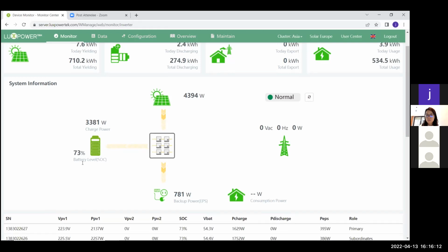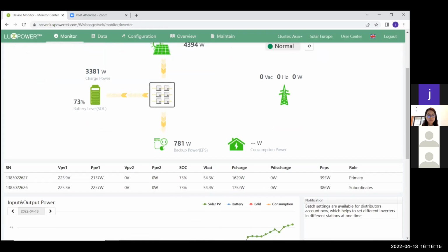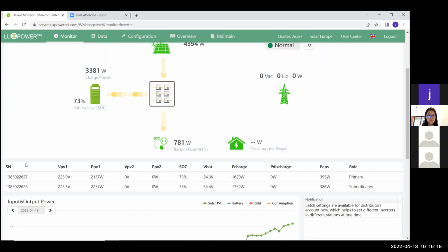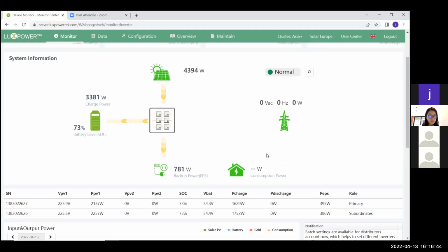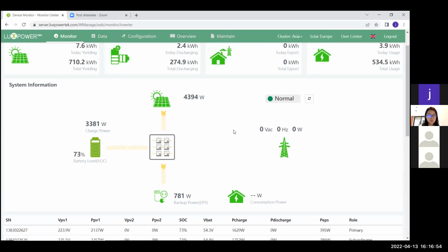This system, as you can see, has not one inverter in the block, but 2 inverters at this moment. This means this system is in parallel. This guy has 2 5-kilowatt inverters running at his house. As you can see, they fairly divide the work between the 2 of these inverters. They're charging at about the same rate, and their discharge, the EPS power as well, is fairly close to each other. So my SNA 5000 units are fairly close on the load division. It divides the load almost perfectly between the 2 as far as possible. So that's quite nice on these specific units.